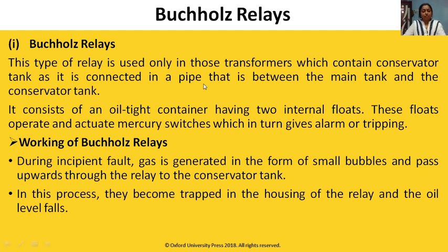It consists of an oil-tight container having two internal floats. These floats operate and actuate mercury switches, which in turn give alarm or tripping. We are using mercury switches. Mercury switches means switches having mercury. Why are we using mercury? Why not other things? Okay, this question I will ask in the live lecture, that you have to answer.